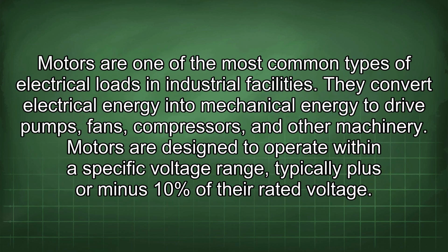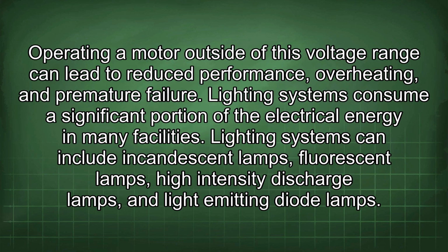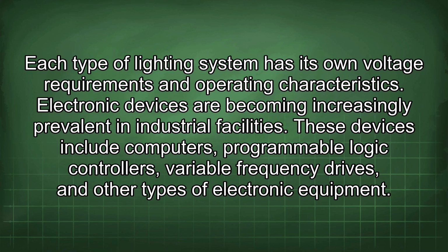Motors are one of the most common types of electrical loads in industrial facilities. They convert electrical energy into mechanical energy to drive pumps, fans, compressors, and other machinery. Motors are designed to operate within a specific voltage range, typically plus or minus 10% of the rated voltage. Operating a motor outside of this voltage range can lead to reduced performance, overheating, and premature failure. Lighting systems consume a significant portion of the electrical energy in many facilities. Lighting systems can include incandescent lamps, fluorescent lamps, high-intensity discharge lamps, and light-emitting diode lamps. Each type of lighting system has its own voltage requirements and operating characteristics.